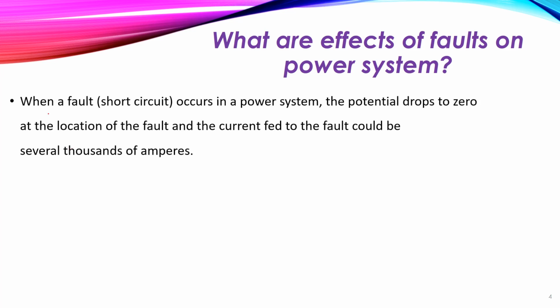Number one, when a fault or a short circuit occurs in the power system, such as when the three-phase transmission line or the three-phase power is connected to the ground, a short circuit will occur. So in this case, since this point of the fault is connected to the ground, the potential or the voltage will drop to zero at the location of the fault. Why? Because it is connected to the ground. Okay, since this point is connected to the ground, the voltage at this point will drop to zero.